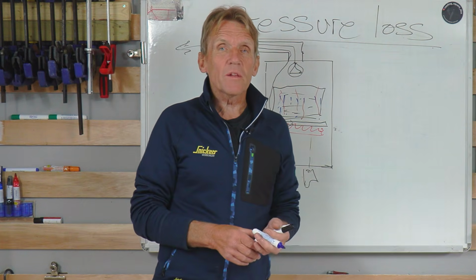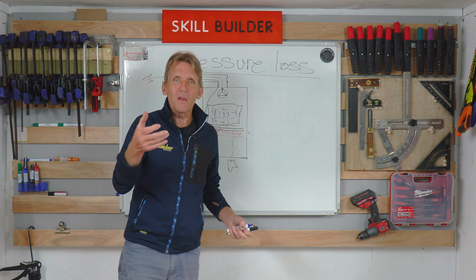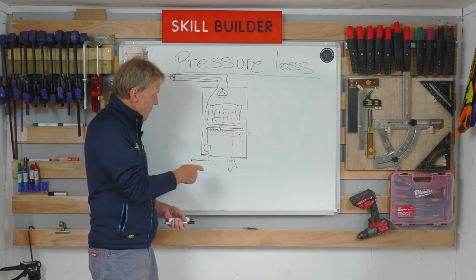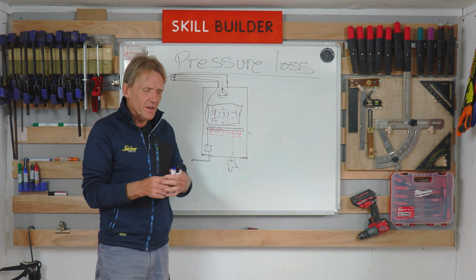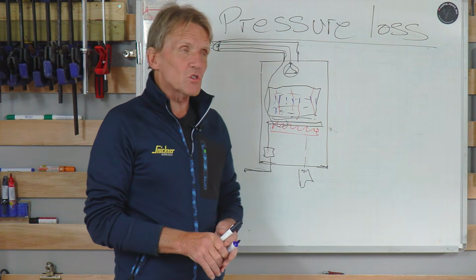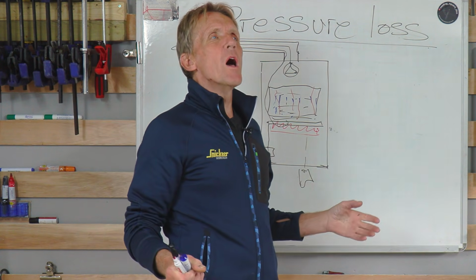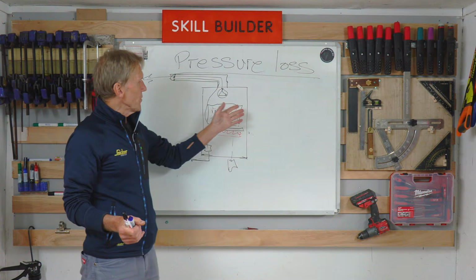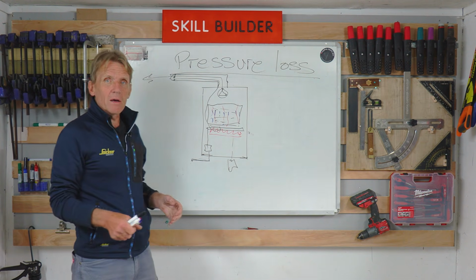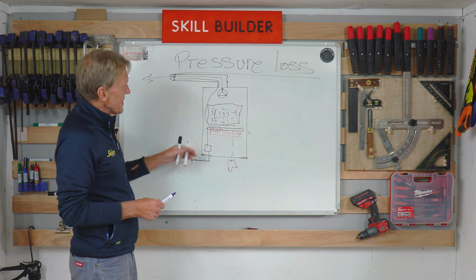And again, this is one of these things where you test that bit of condensate, and if you've got something smelly or you've got some corrosion inhibitor inside the system, you can very often just pick up the smell of it from that condensate. The other place that you will find it is if you have a little bit of a sniff around the boiler, because if you put something smelly in there, you will be getting a nice aroma. So if you smelled eau de cologne or something like that, and you've been foolish enough or rich enough to put that in the system, you would smell it coming out of the boiler flue. So that's an indication of the fact that you've got a leaking heat exchanger.